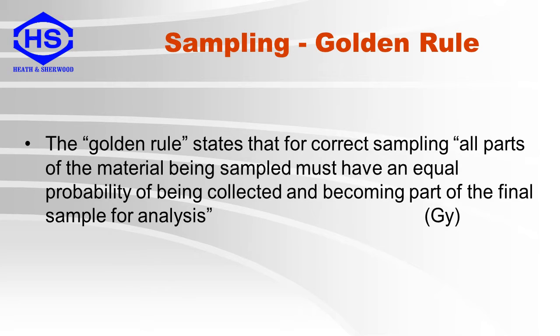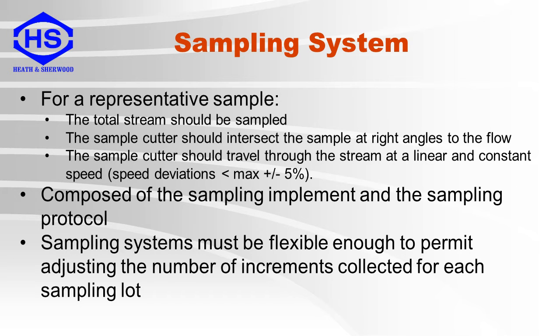In the sampling basics presentation we discussed the golden rule for sampling, which states that for correct sampling, all parts of the material being sampled must have an equal probability of being collected and becoming part of the final sample for analysis. For a representative sample, the total stream should be sampled, the sample cutter should intersect the sample at right angles to the flow, and the sample cutter should travel through the stream at a linear and constant speed.